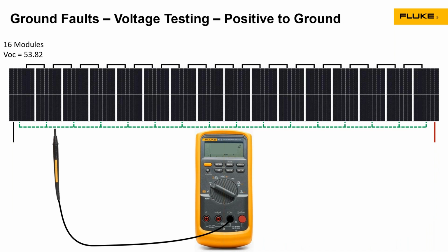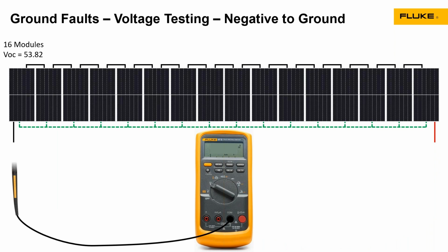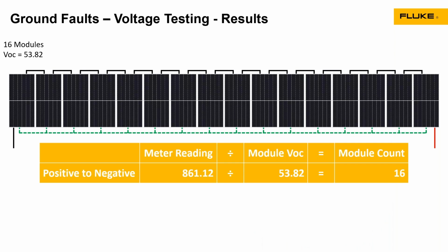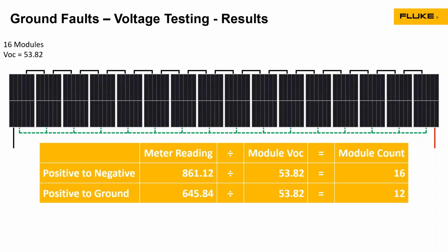If I measure from the ground to the positive, I should get 0 volts, but in this case, I get around 645 volts. If I measure from the negative to the ground, I should also get 0 volts, but in this case, I got around 215. I'm going to record all these results and do some analysis. So when I look at my results, from my positive to the negative, I get around 861 volts. Divide that by 53 volts in the module, and I get 16 modules. And that's never going to be exact. I'm going to get some variations there due to environmental conditions, the system design, and how it's put together, but it's getting pretty close to 16.